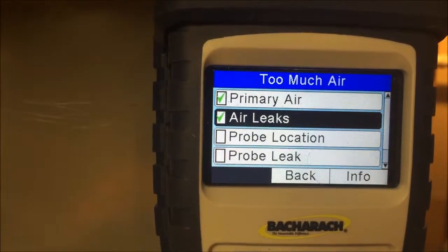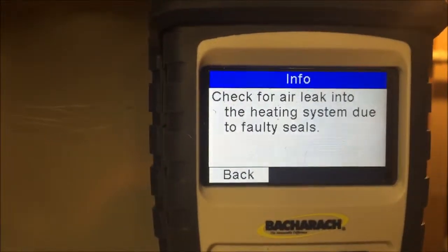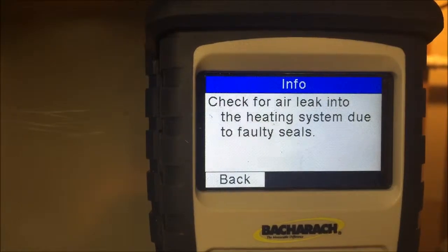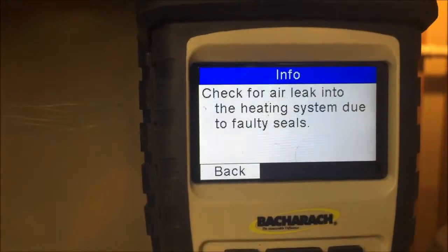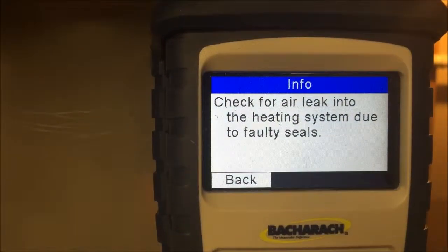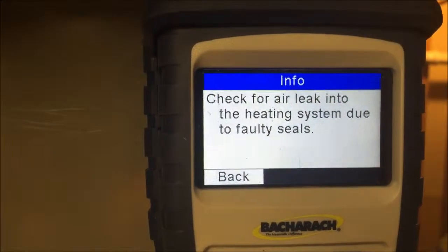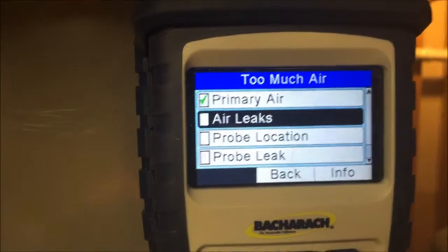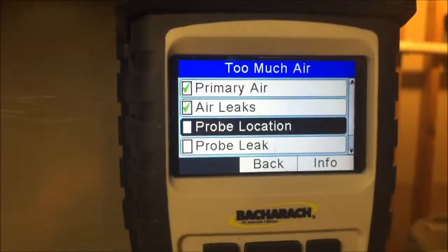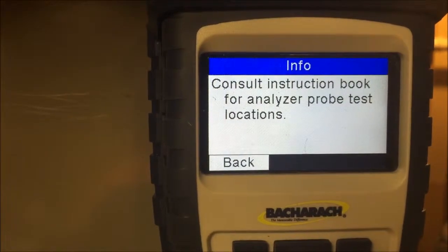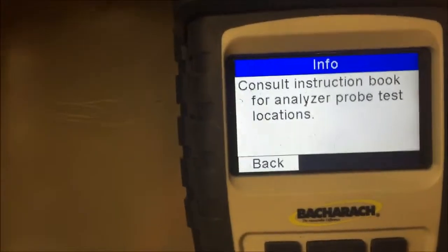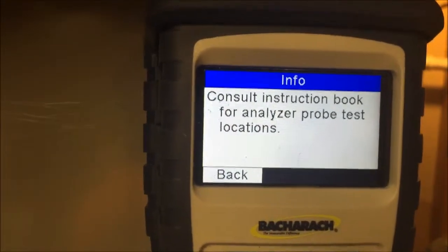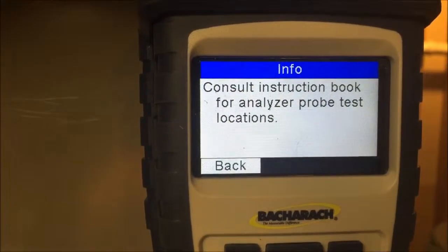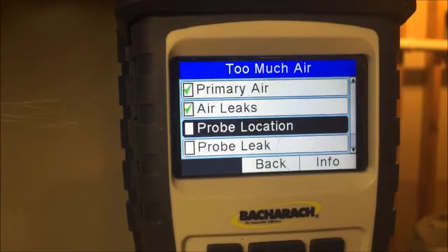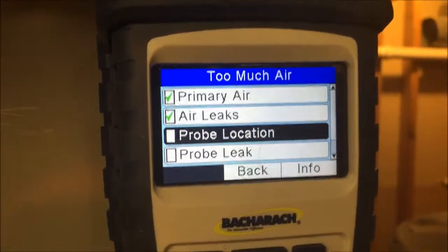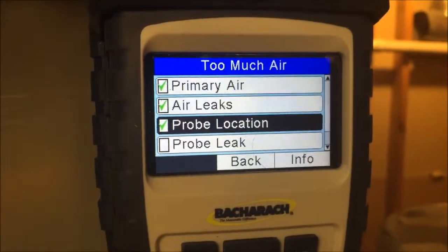Air leaks. Check for air leak into the heating system due to faulty seals. Okay, checked everything. The unit's tight. We know it's good, so we're gonna say that is good, not a problem. Probe location. Okay, the probe location is in the right location. As far as how far it is in, yeah, you and I know that it's wrong, but let's say for test's sake that it's good. So I know that the probe location is proper, and I know it's the right height away from the draft inducer, so that's good.